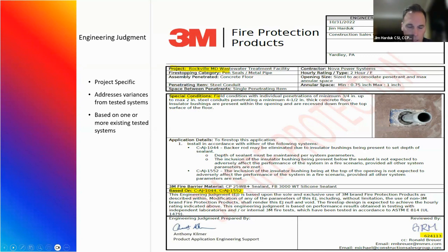And then it'll be based on one or more UL tested systems. And if you look towards the bottom of the page there on the left, you see this is based on 2 UL tested systems, CAJ 1044 and CAJ 1552. So that's not uncommon. I have been involved with engineering judgments where we've probably based it on 3 or 4 different tested systems. And then in the lower right-hand corner, there'll always be a number. That is the engineering judgment number. These get logged in and kept on file at 3M.